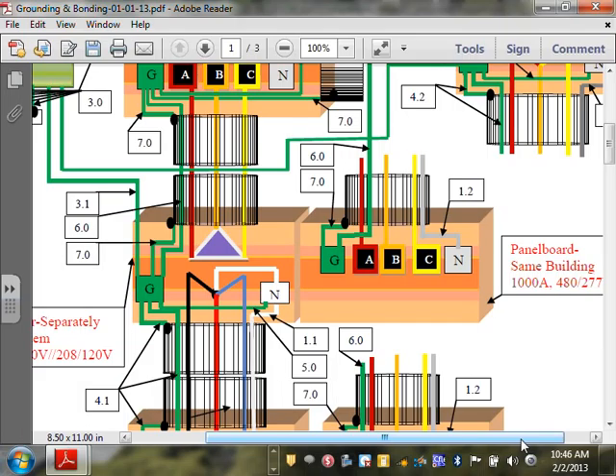Now we're getting into grounding bushings. One second, absolutely. That will be your number 7 here. See that number 7 here? So let's say we're having an equipment grounding conductor coming to the switchgear, landing on the ground bar in the switchgear. I have my neutral bar, the neutral bar completely isolated from the box or the frame, and the two are not tied together by code. They must not be tied together. You guys are familiar with this, right? Does that make sense for all of you? I'm repeating things that you know.